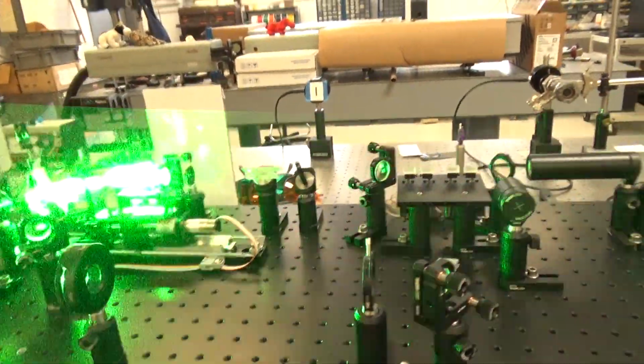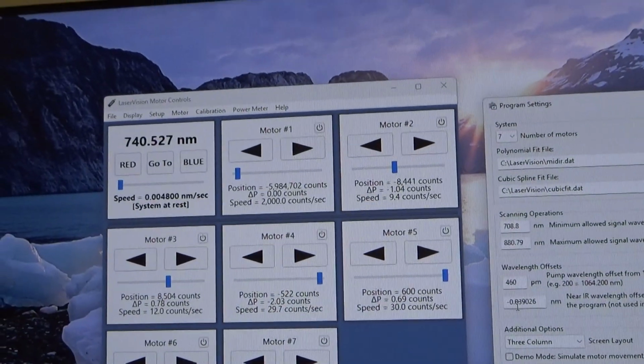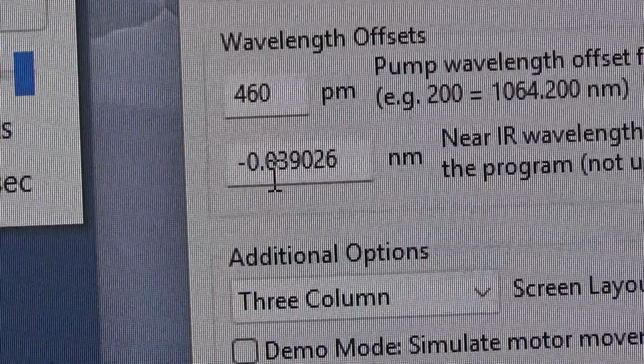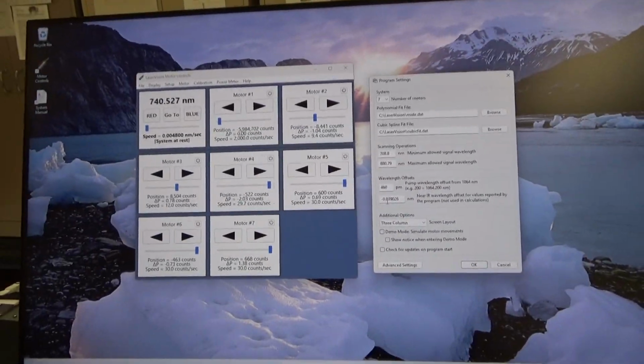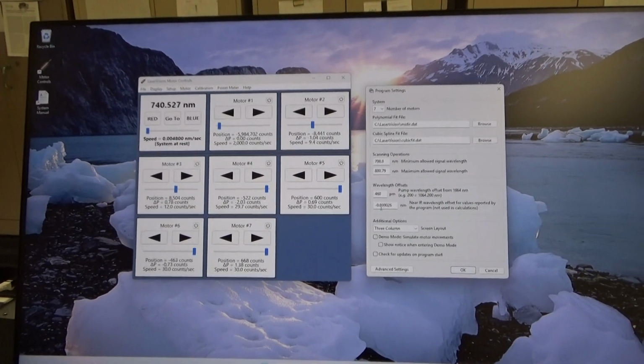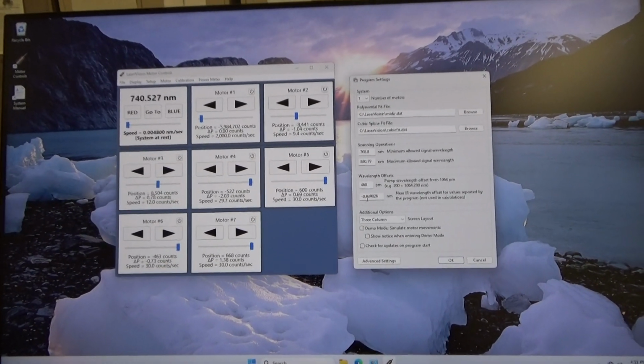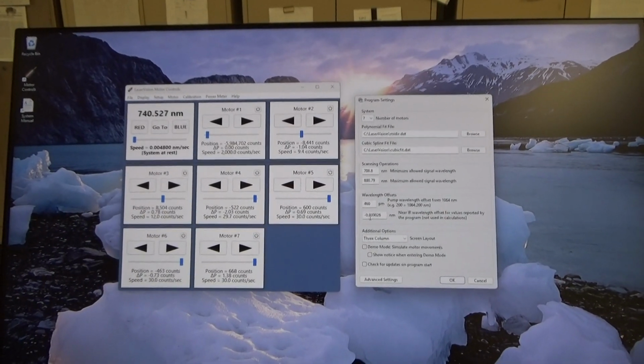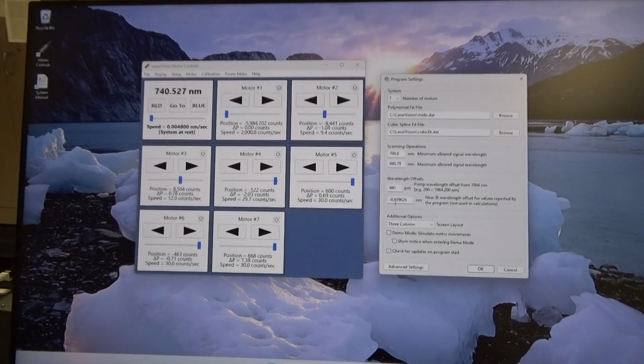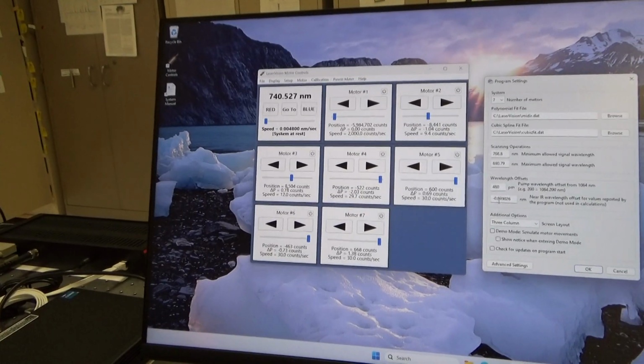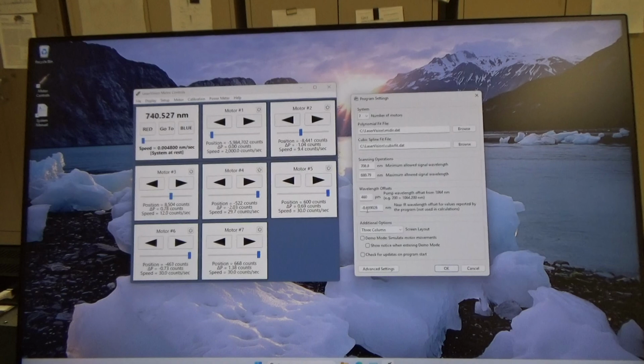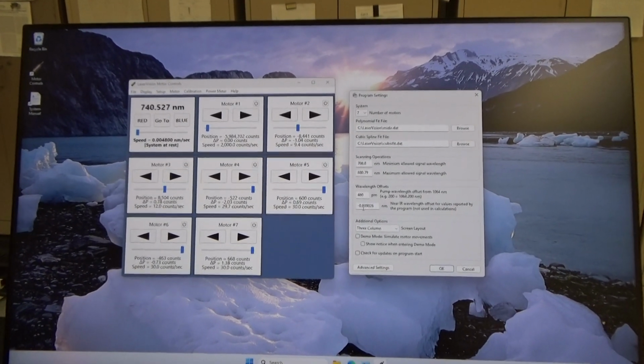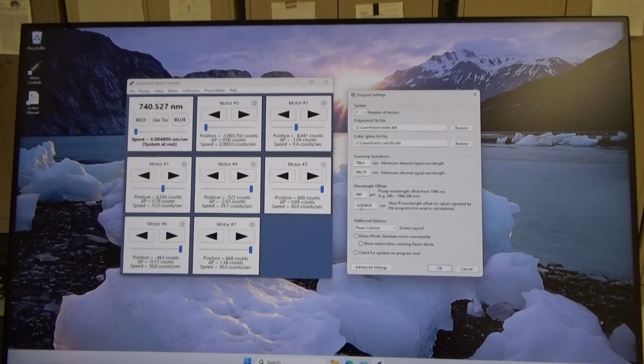So once you have the system up and running at some wavelength and you've optimized it and you can determine what that wavelength is, all you need to do to recalibrate the system is find the difference between the current displayed wavelength and what the wavelength should be displaying, and enter that value in as an offset into the system. Using this velocity scanning mode, I can on the fly optimize energy for the system without changing the tuning characteristics. The tuning characteristics remain unchanged. This is not true if you've got a lookup table, and that's one of the main reasons why I chose this tuning method for these systems: you don't have to suffer through generating tuning curves every time you want to calibrate the system.